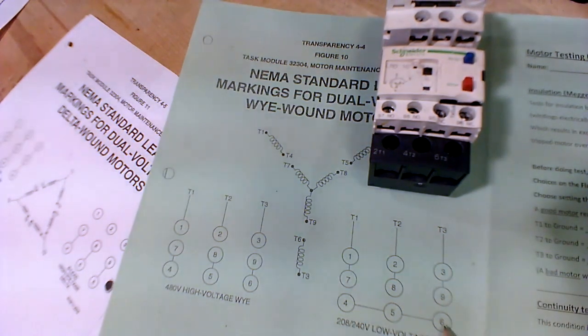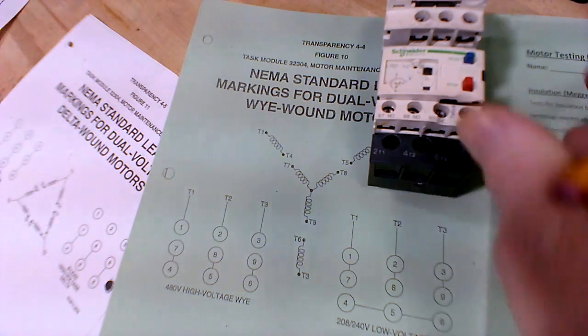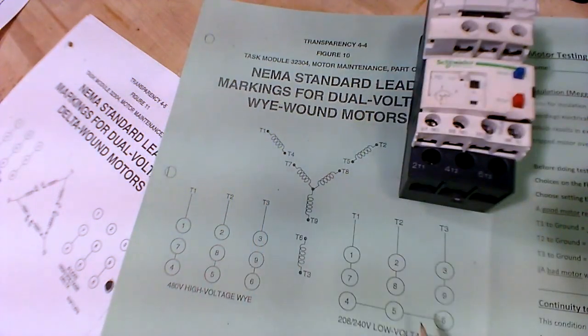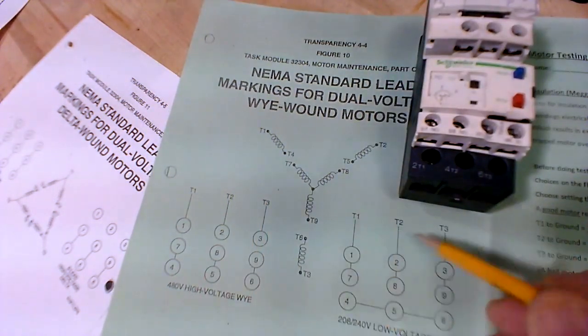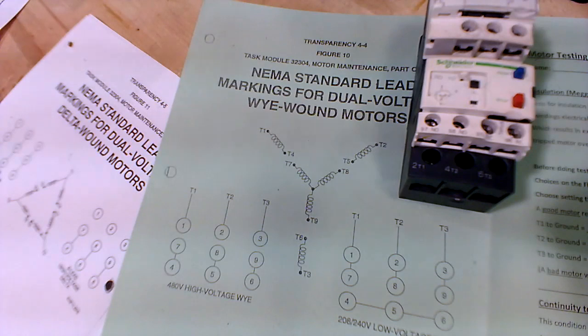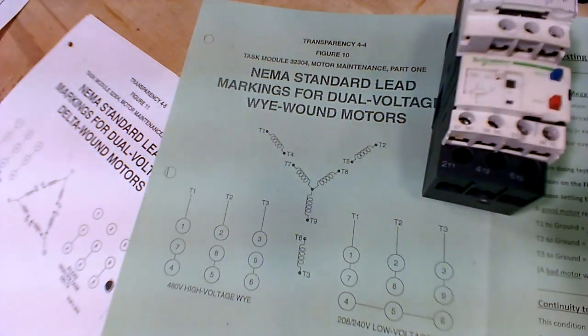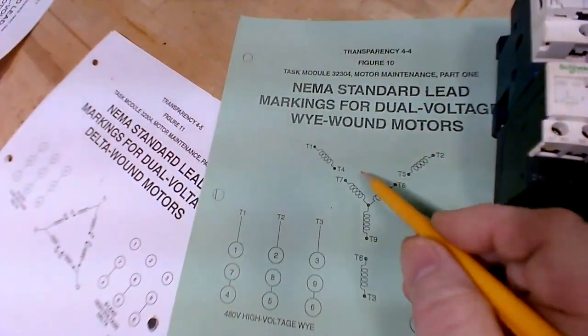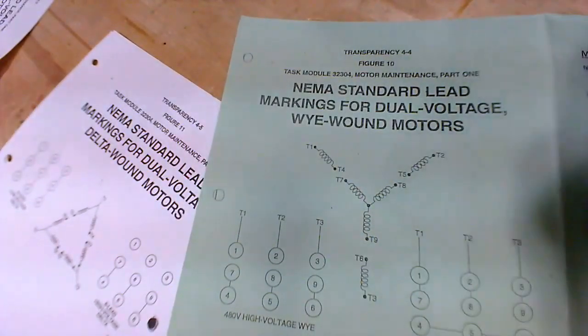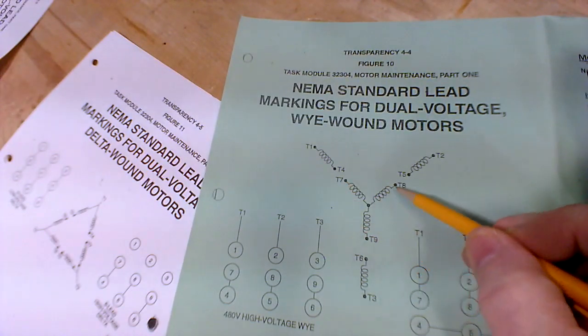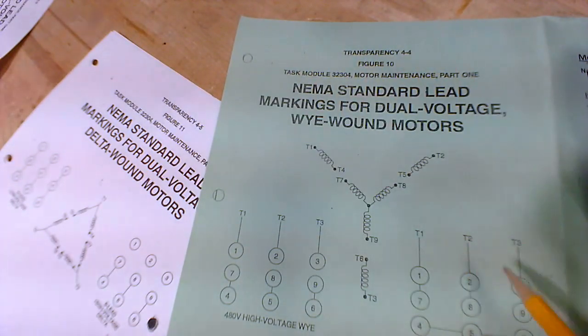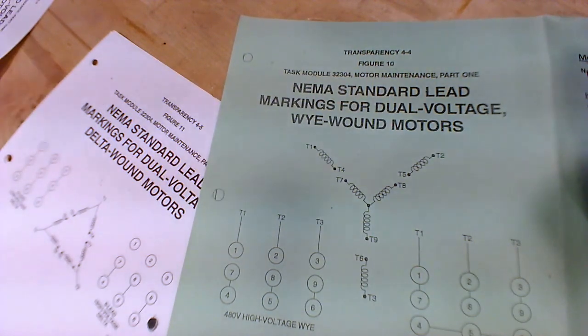Then you take 4, 5, and 6, and you bundle them together, and you don't connect them to the power line. They are just isolated, bundled together, 4, 5, and 6. That's 3 wires together. So if it's a common Y-wound motor and you're on low voltage, each wire nut has 3 wires per wire nut. Okay?